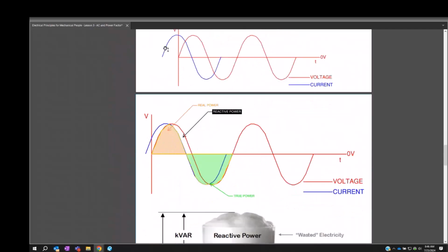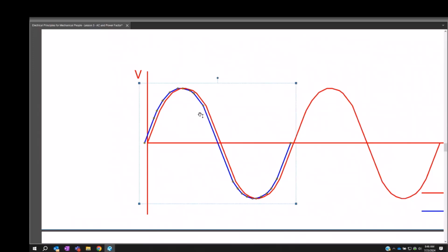Well, I want to pull this curve back. I want to pull this back, and get more real power out of it and less reactive. Exactly. So I'm going to counteract the induction of those motors with a capacitor bank. And I'm going to pull this curve back this way. Gotcha. Yes. But at the end of the day, for it to be an induction motor, there has to be some kind of reactive power. You can close the gap to show less reactive power, but reactive power is needed no matter what.